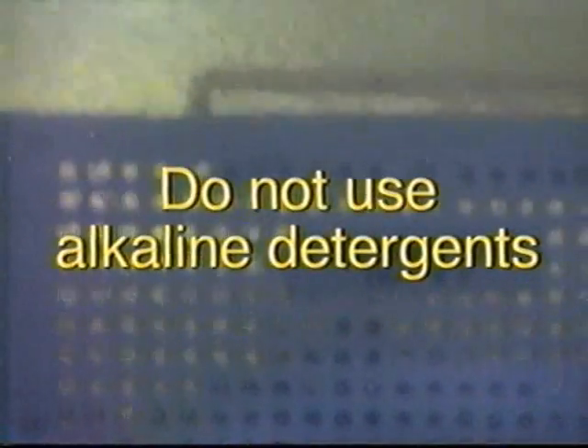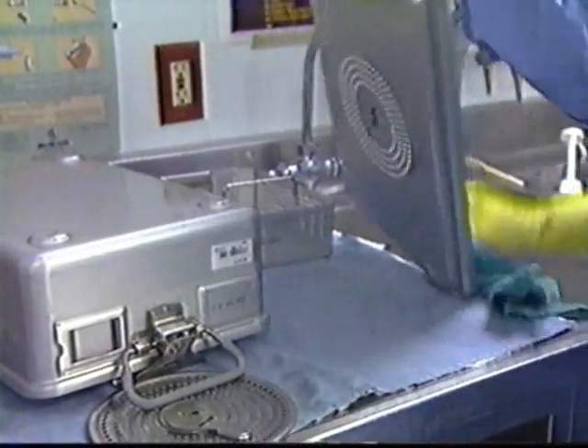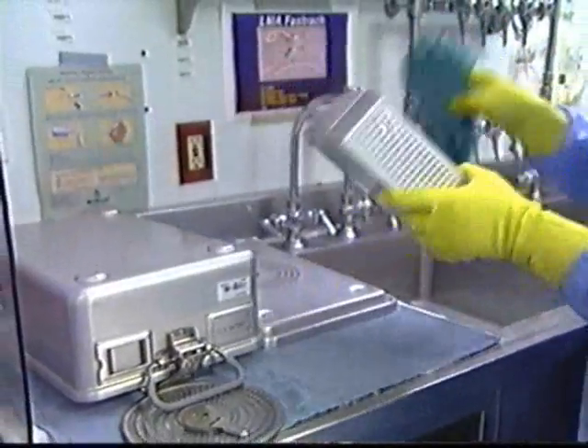Caution! Do not use alkaline detergents as they will oxidize the aluminum of the container. If necessary, you may clean SteriTite container components manually with a soft cloth and a pH neutral detergent. Make sure to remove all detergent agent with a thorough rinsing.